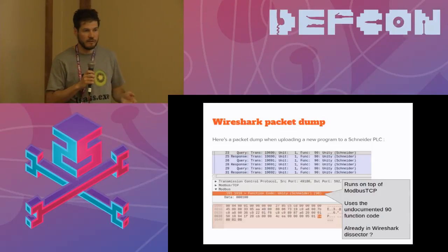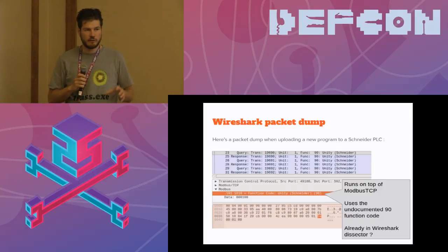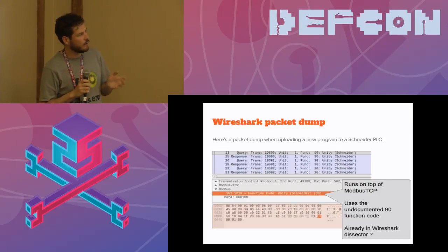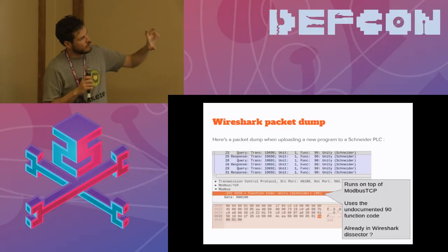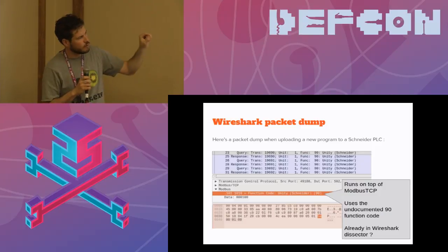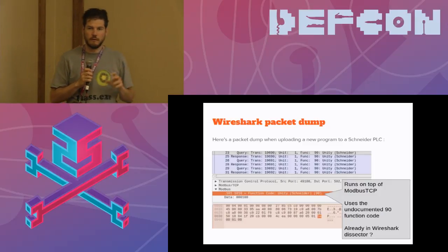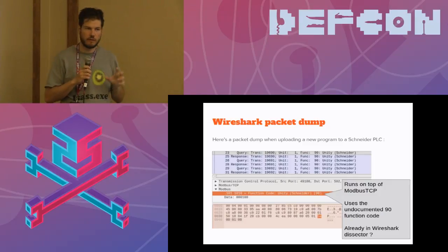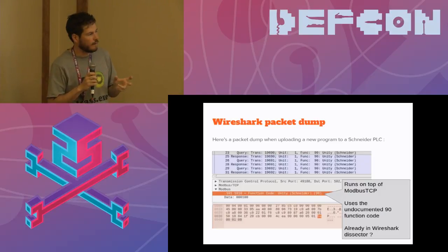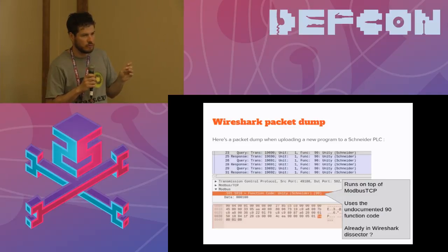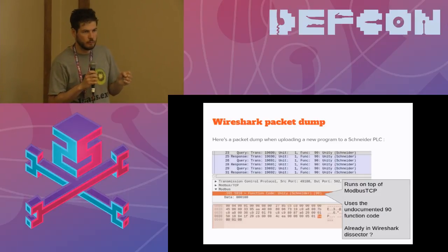How do we discover this? It's quite simple. You install a demo PLC, install Unity Pro, launch Wireshark, and look at the packet dump. Here's a packet dump when I log in to a PLC and upload a new program — it runs on top of Modbus TCP with function code 90, and it's already part of the Wireshark dissector. The use of Modbus function code 90 is not something new. I had a chat with Alexei Lagoutte, a Wireshark developer in France, and he was kind enough to add this to the Wireshark Modbus TCP dissector. So now you can detect when someone is performing admin actions on a Schneider PLC.